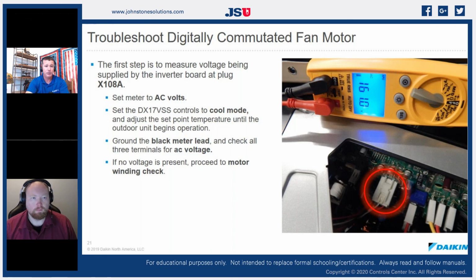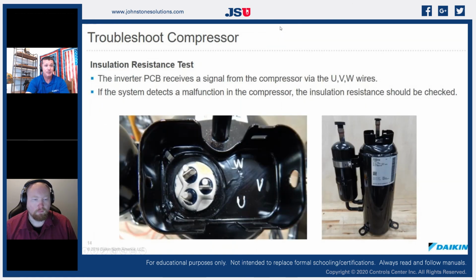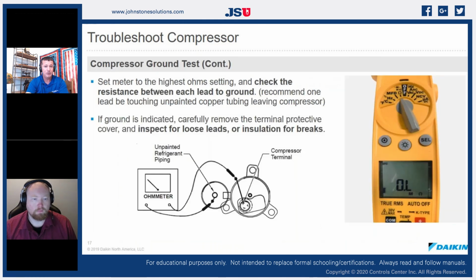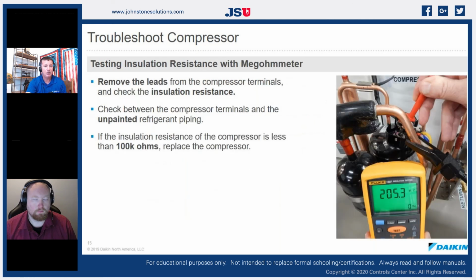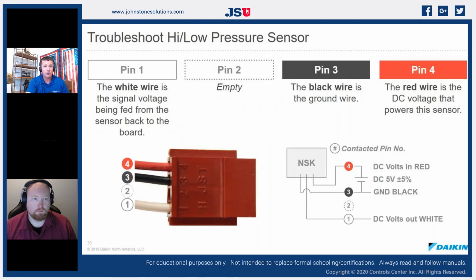We can check the voltage tune, make sure that all 3 legs are getting proper voltage. And then we can check to make sure that they have even resistance between them for the condenser fan motor and for our compressor. So we're simply going to check those from winding to winding. And then, like we used to do before on our permanent split capacitor compressors, we're going to check the insulation of our motor. We're going to check mega ohms from ground to the conductor. If we have less than 100 k ohms, we've got bad insulation on those windings. But that's really about the only thing we're ever going to do. We're hardly ever going to burn those things up. So we're just going to check resistance between them.